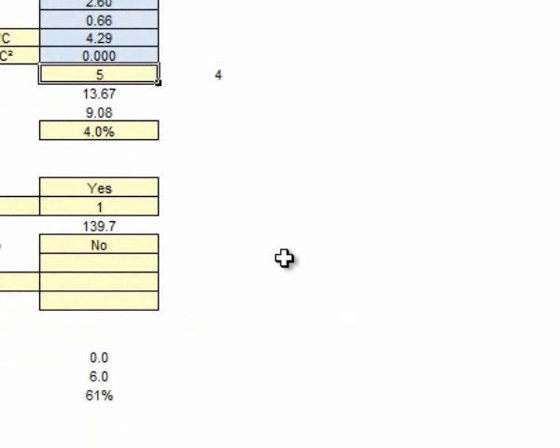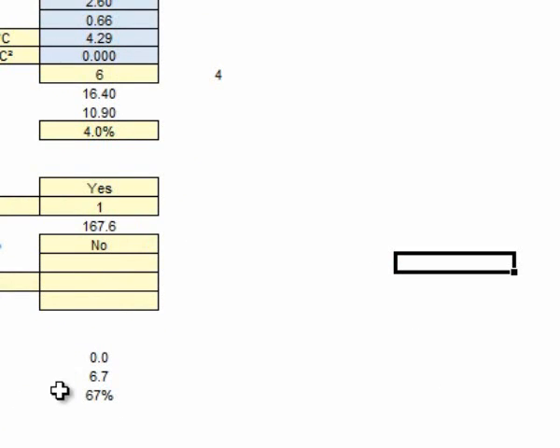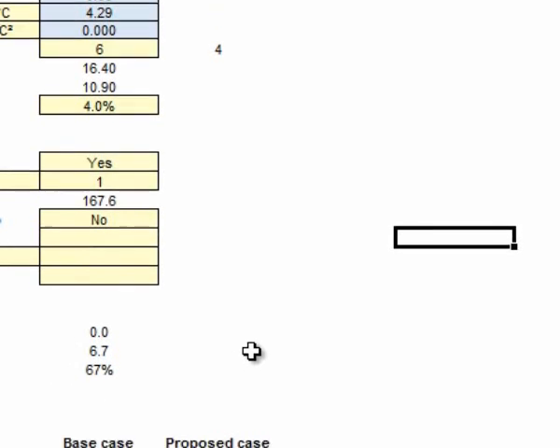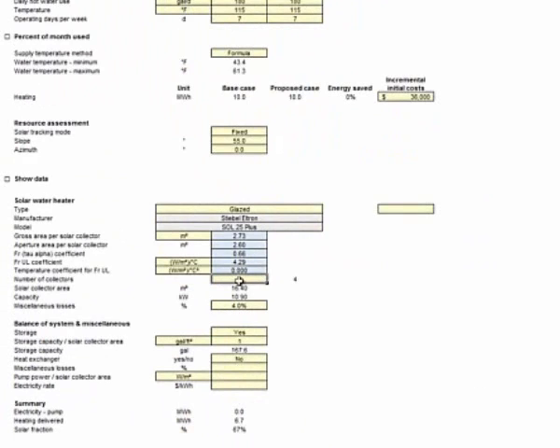So a good rule of thumb would be to try to get your number of collectors to the storage sampling size to give you a more realistic value of offloading. This is what solar fraction is, the percentage of the sun in the solar heat system that we're going to use to heat this water. So how much is going to be run by, say, the natural gas or electric hot water, and how much is going to be coming off of the solar thermal systems. I have a total of 6 modules here.